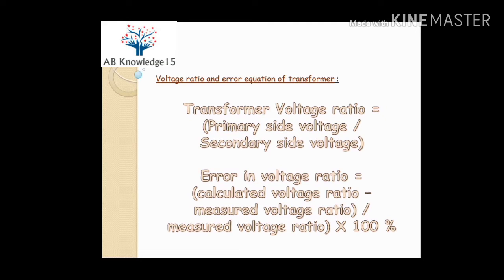Now coming to the voltage ratio and error equation of transformer. The transformer voltage ratio equation is simple: primary side voltage divided by secondary side voltage. The error equation for the voltage ratio test is: calculated voltage ratio minus measured voltage ratio, divided by measured voltage ratio, into 100% for calculating it into percentage form.